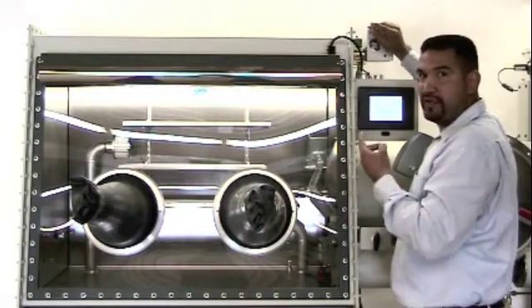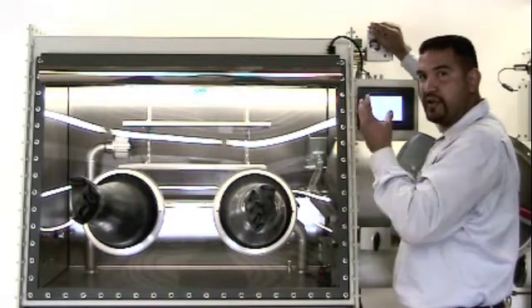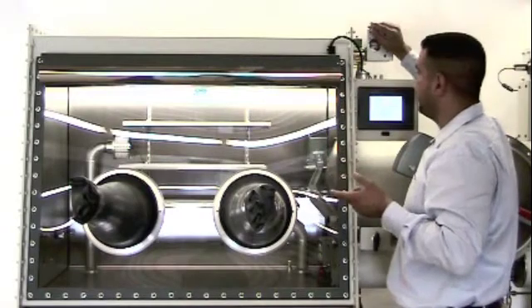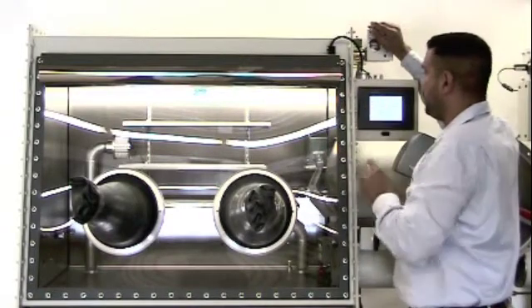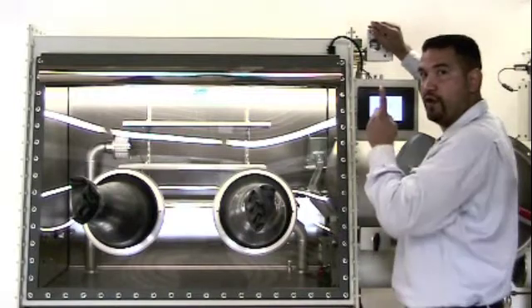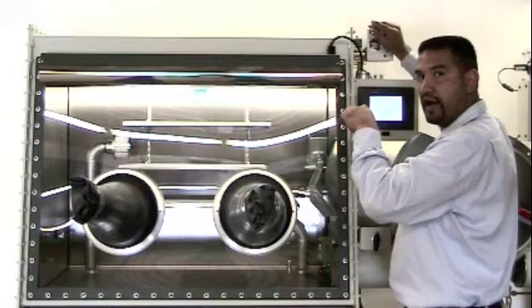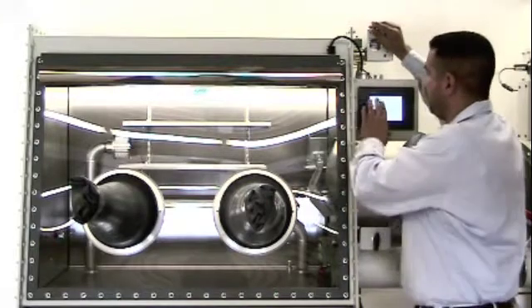Turning the span potentiometer clockwise increases, whereas counterclockwise decreases. In this situation here, we are at 30.2%, so we are pretty high. So we want to turn counterclockwise to decrease that reading.